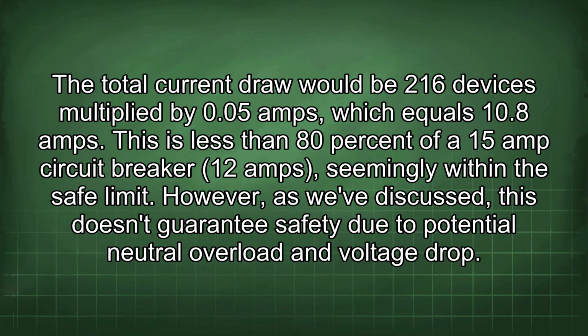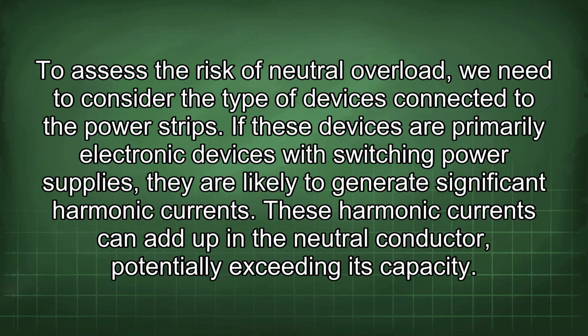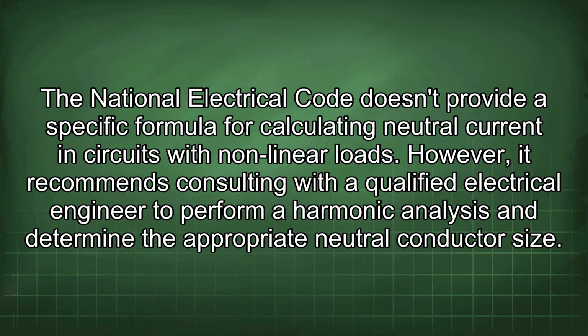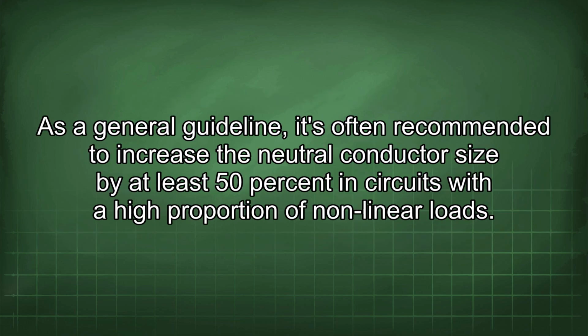However, as we've discussed, this doesn't guarantee safety due to potential neutral overload and voltage drop. To assess the risk of neutral overload, we need to consider the type of devices connected to the power strips. If these devices are primarily electronic devices with switching power supplies, they are likely to generate significant harmonic currents. These harmonic currents can add up in the neutral conductor, potentially exceeding its capacity. The National Electrical Code doesn't provide a specific formula for calculating neutral current in circuits with nonlinear loads. However, it recommends consulting with a qualified electrical engineer to perform a harmonic analysis and determine the appropriate neutral conductor size. As a general guideline, it's often recommended to increase the neutral conductor size by at least 50% in circuits with a high proportion of nonlinear loads.